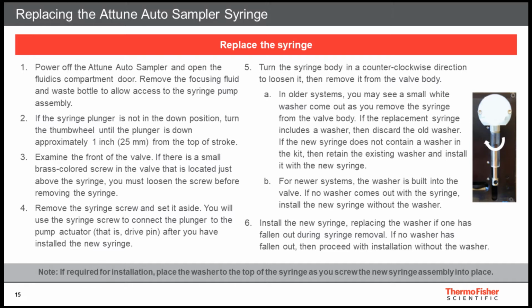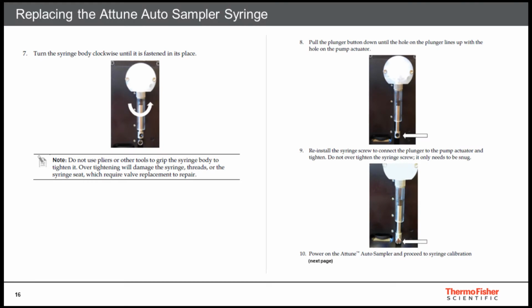Lower the plunger, if the plunger is not already down, by turning the thumb wheel located towards the left of the syringe. Remove the screw retaining the plunger using a flathead screwdriver. Next, unscrew the syringe. After you are convinced that the new syringe is not seized by pushing and pulling on the plunger, install the new syringe in the reverse order to how the previously installed syringe was taken out. After a few startups, please check to ensure that the syringe is tight. If loose, please tighten.